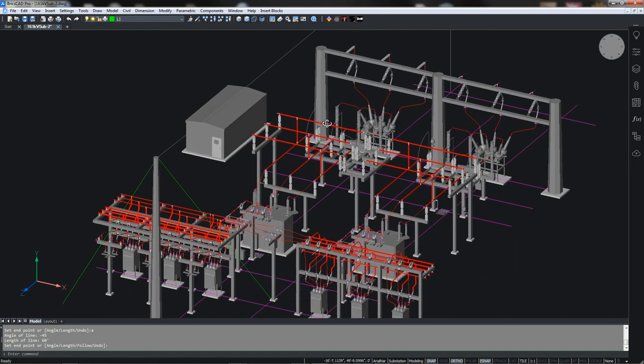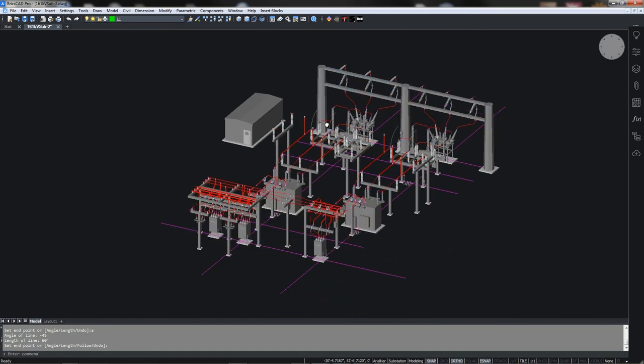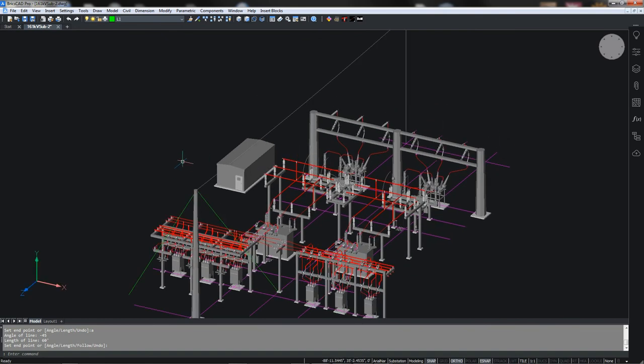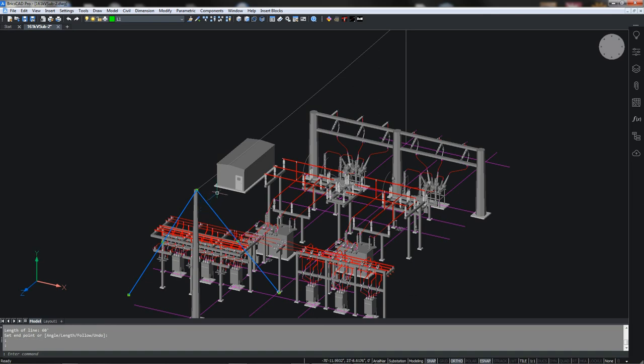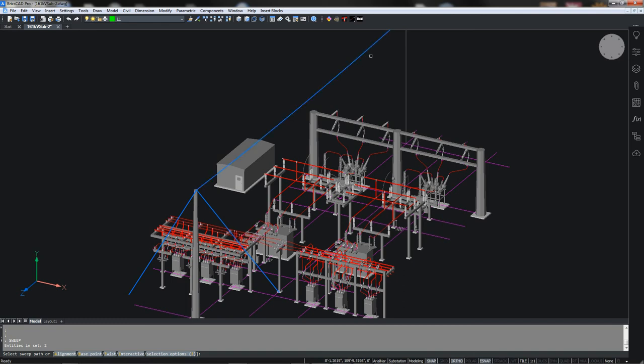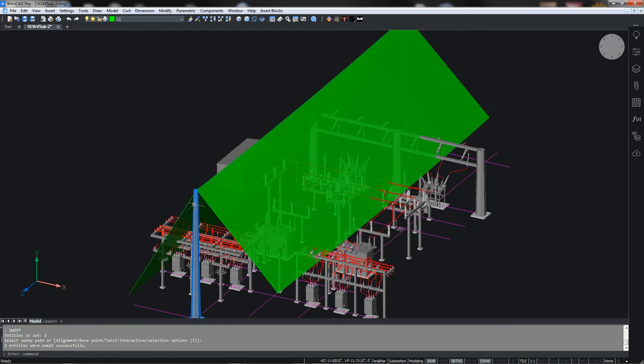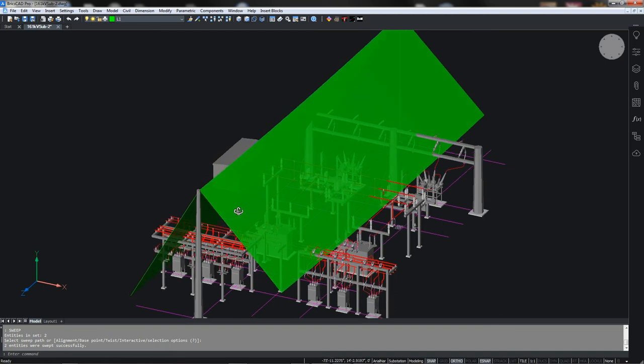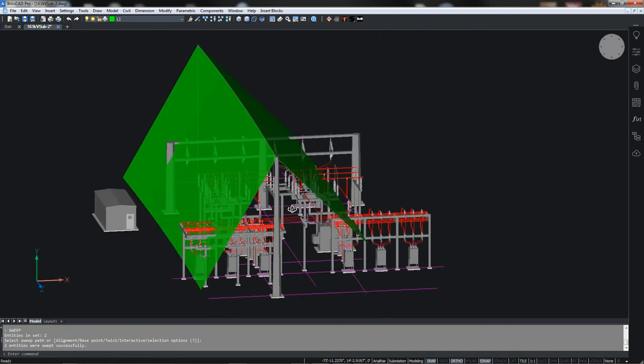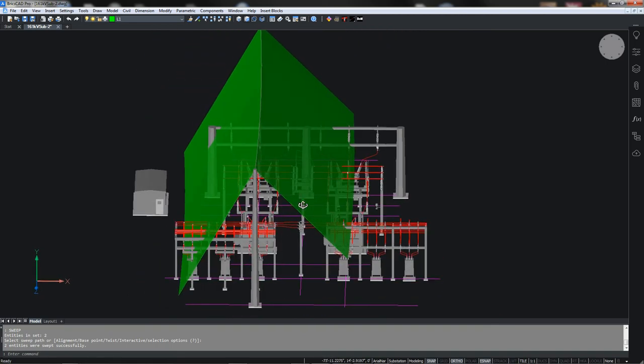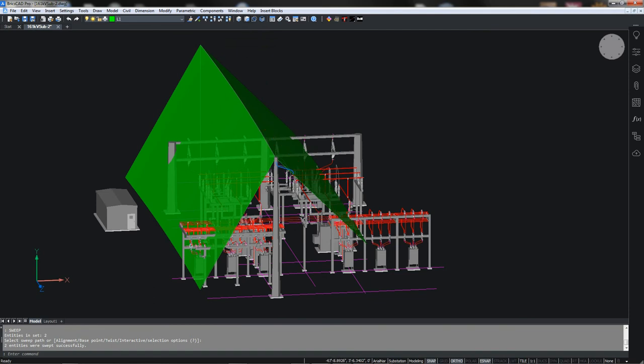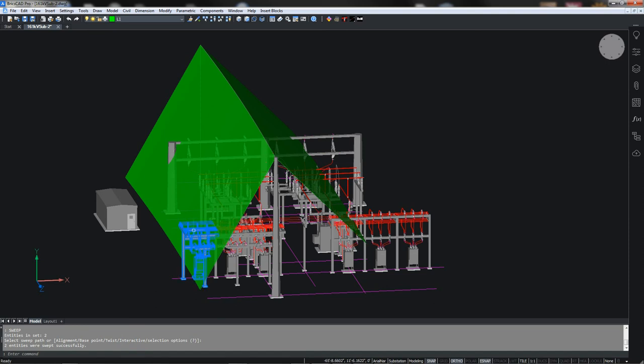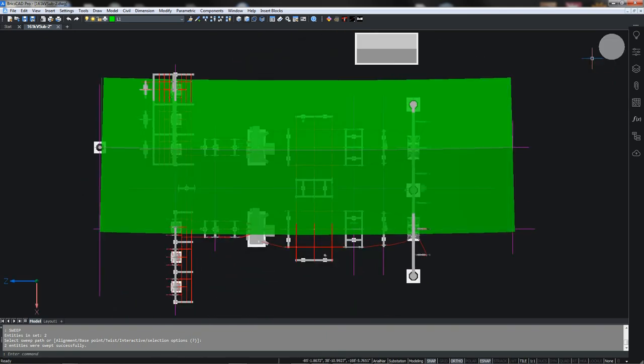I think that will be adequate for what we're doing. Now we have our two shield lines. Now we need to make a surface out of those. There's a simple command in AutoCAD and BricsCAD called sweep. So we'll select those two lines and tell it to sweep, and it will ask for the path that we want to sweep it on, and the path would be our overhead ground wire. Here you see we've got two nice surfaces that show the coverage underneath. Unfortunately we have a portion of this bus that is sticking out in the unshielded area.